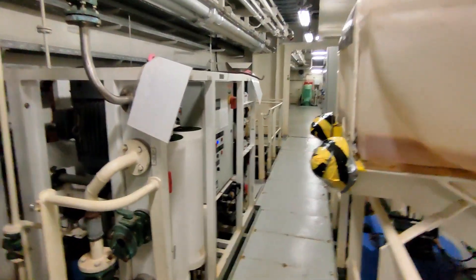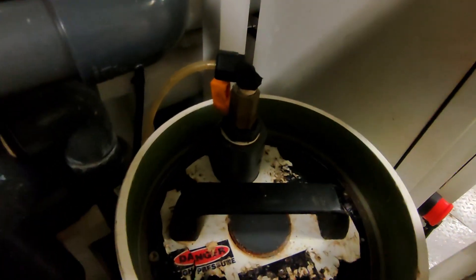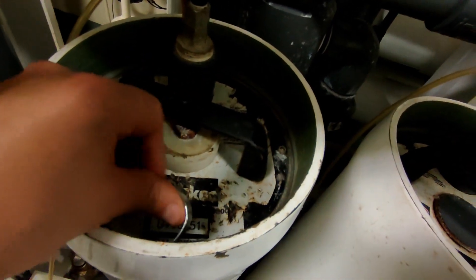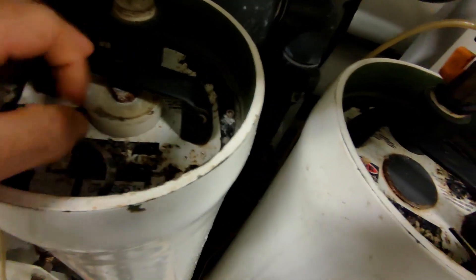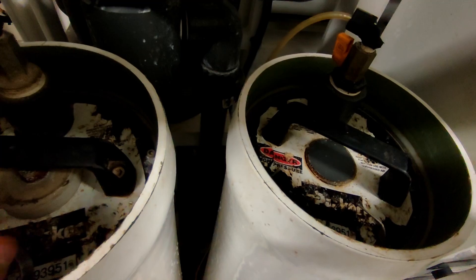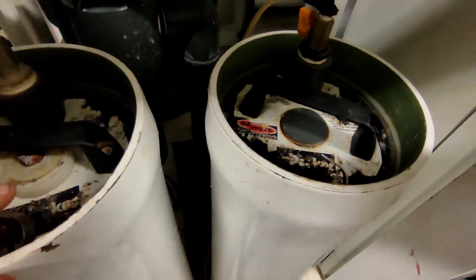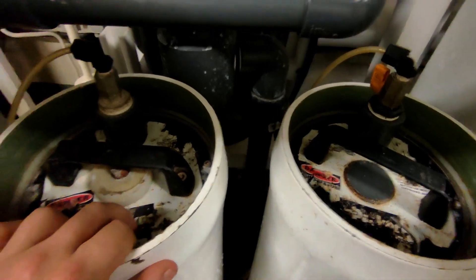So here we are, that's the new filters back in. As you can see the snap ring is down all the way around. A good tip here is to make sure you insert the snap ring, put it in somewhere with plenty of access to pull away. If you had the snap ring ended up over here, then it can get pretty difficult to try and pull out. The last thing to do now is to vent these off, get rid of all the air inside.